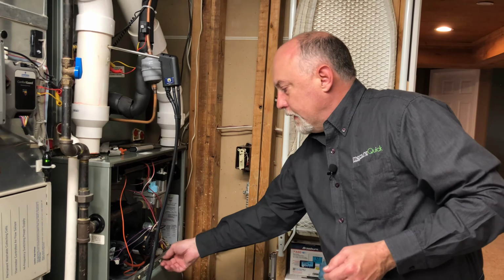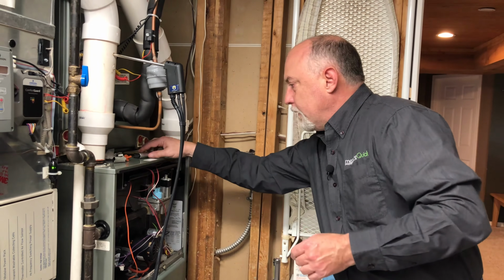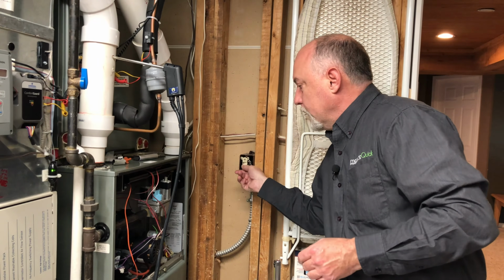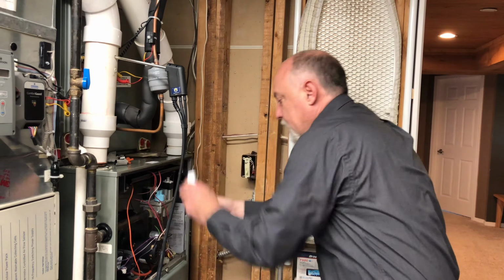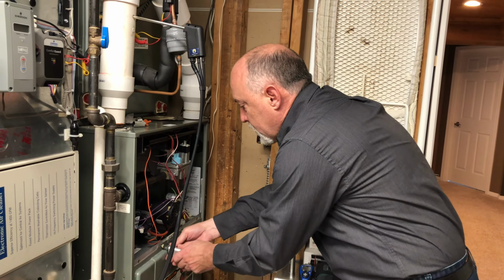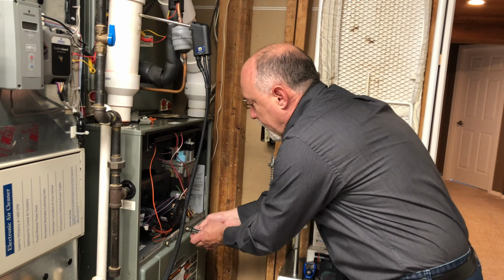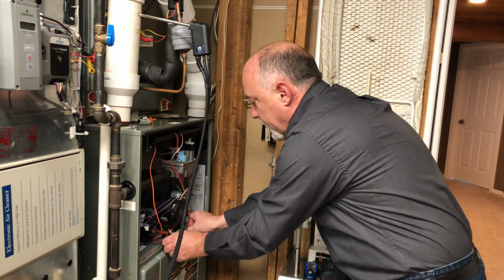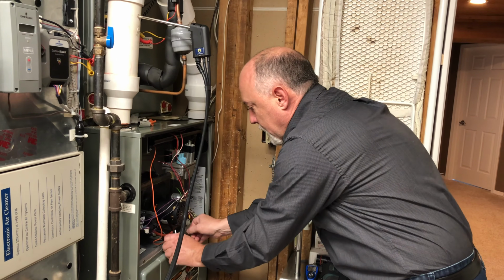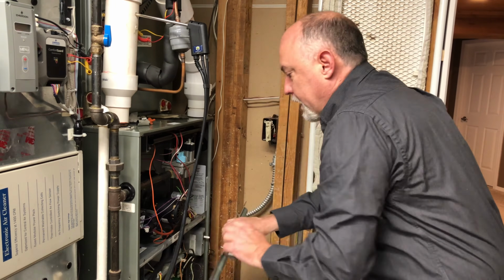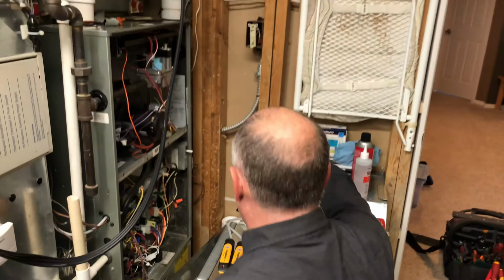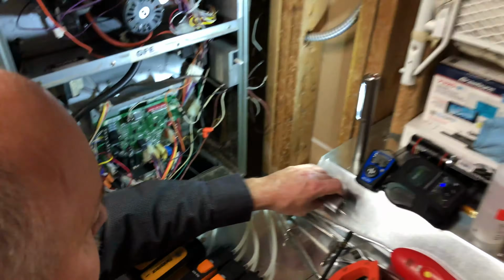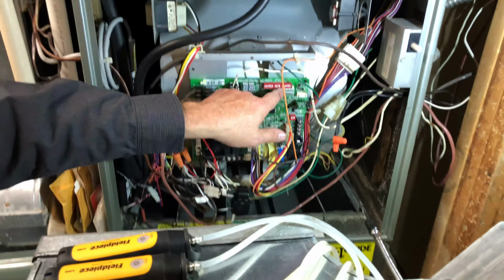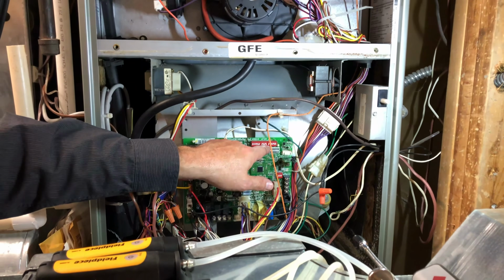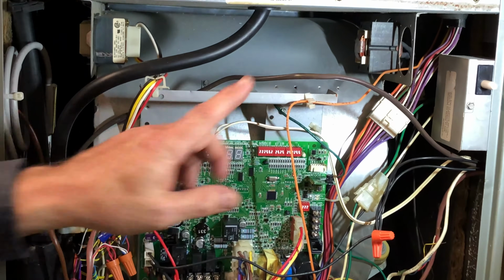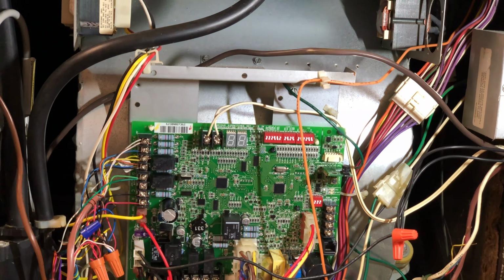We'll go ahead and let that finish cooling down, and then we're probably cool enough here, and then we'll do a quick inspection here. So what I want to do, and a couple things I'll show you here, is I got set up preliminarily. I have the videographer come over to the other side of me here. All right, so this furnace is a full modulation furnace, but it's got a test mode here, and I set the dip switches up so that it's got 100% call for heat for 60 minutes.